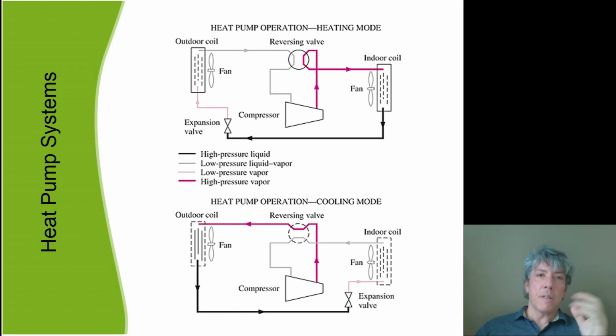Well, the reason for that is heat pumps have an automatic defrosting cycle, because when you form ice on the surface of that coil, you've got to get it off to continue the cycle. And so they literally turn the heat pump into air conditioning mode in order to defrost. Now, I programmed my system custom so that air goes across the indoor coil to make the defrosting happen really quick. I probably should change that because the heat pump's probably a pretty dumb one that just times defrosting every so often. But in most heat pumps, when they're set up correctly, the indoor blower does not blow. What happens is some heat is extracted from the indoor coil in order to defrost the outdoor coil, but you don't blow air across it so that people don't feel like you're air conditioning their homes in the wintertime.